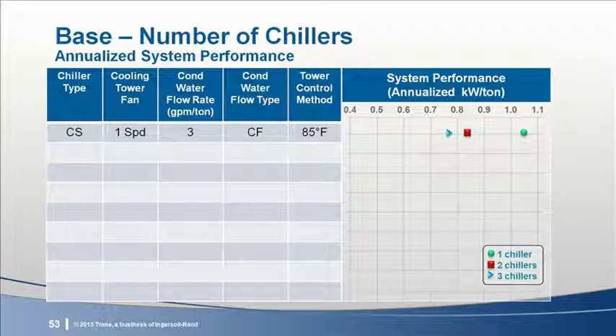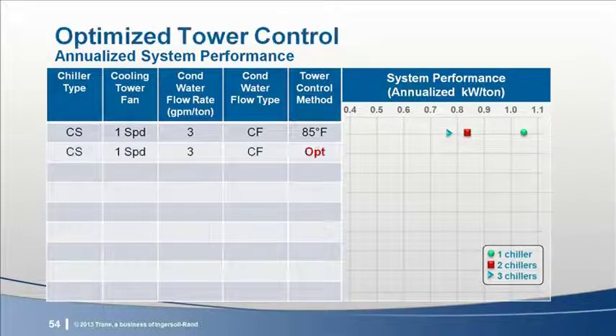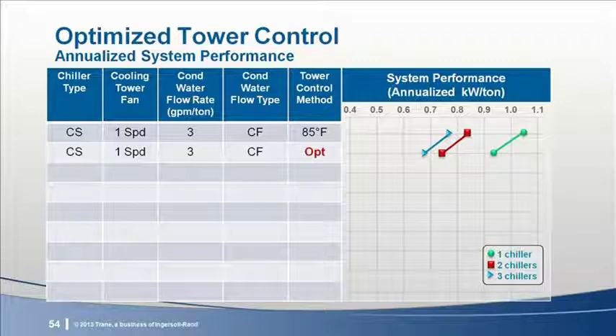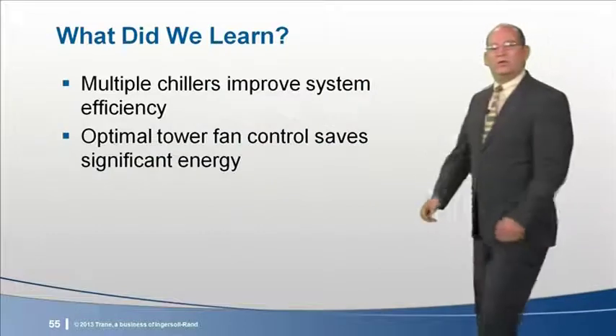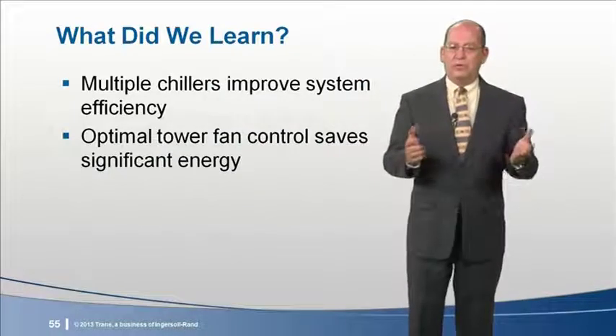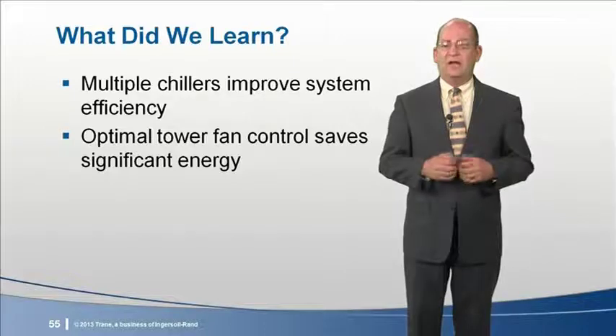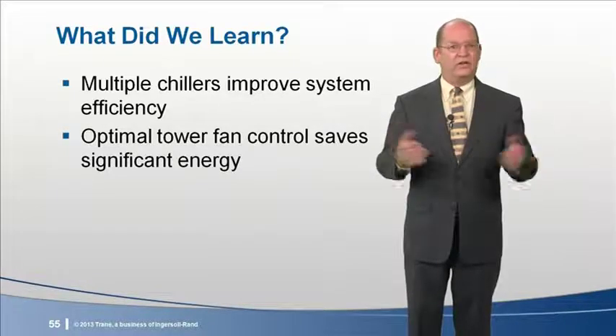Now this makes sense, since the chillers themselves will likely operate in a more efficient mode, and ancillary energy consumed by constant speed equipment is much higher for 1 large chiller than it would be for 3 smaller chillers. Our next alternative only optimizes the cooling tower set point. We see that this reduces the annualized kW per ton about 0.1 in all cases. So our first conclusions are that multiple chillers improve system efficiency and optimal tower fan control saves energy.